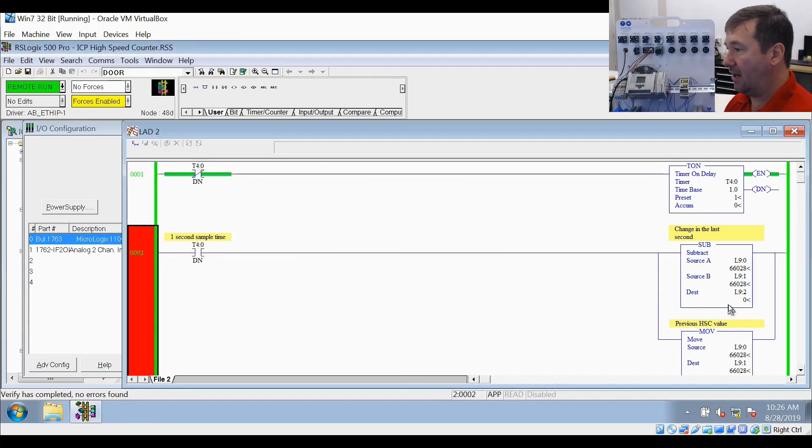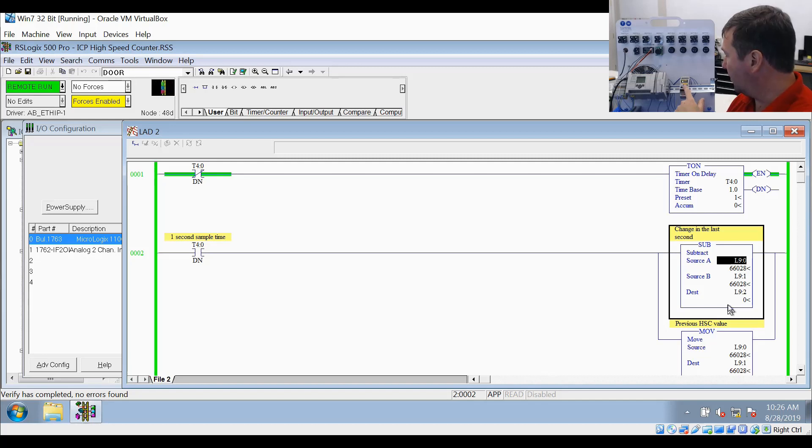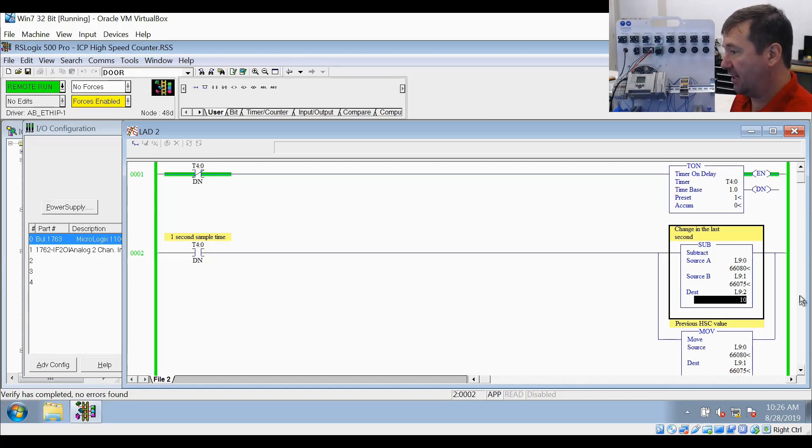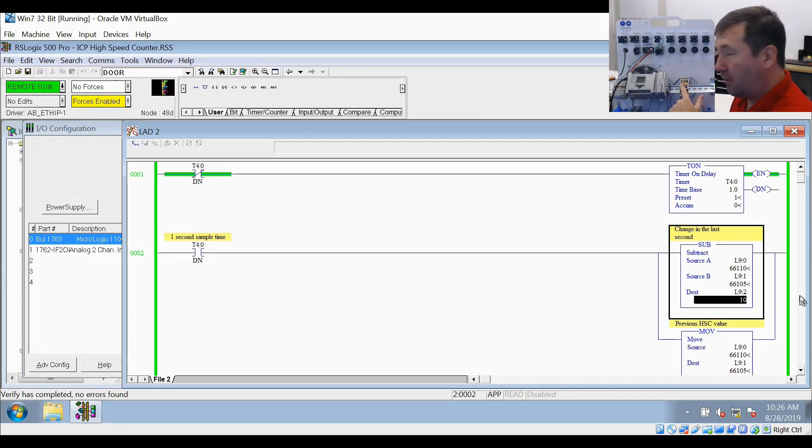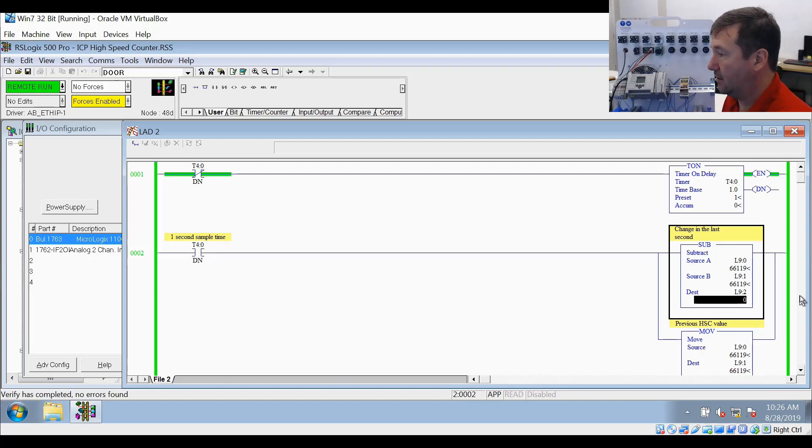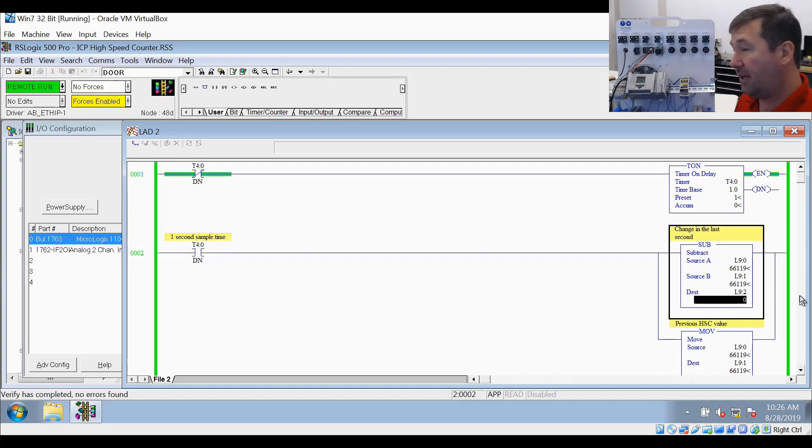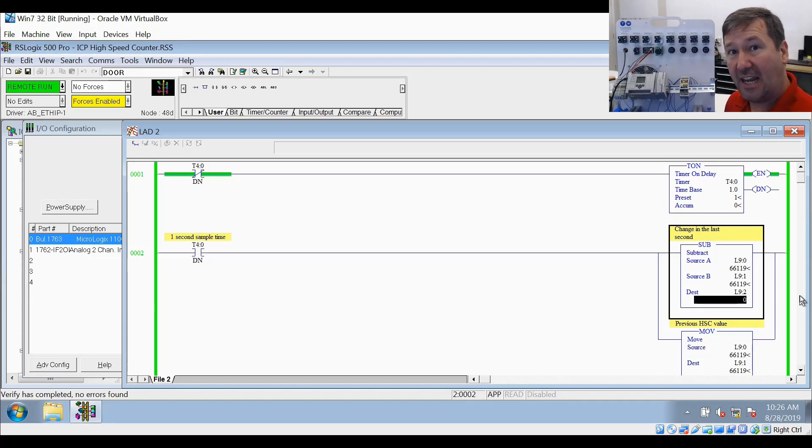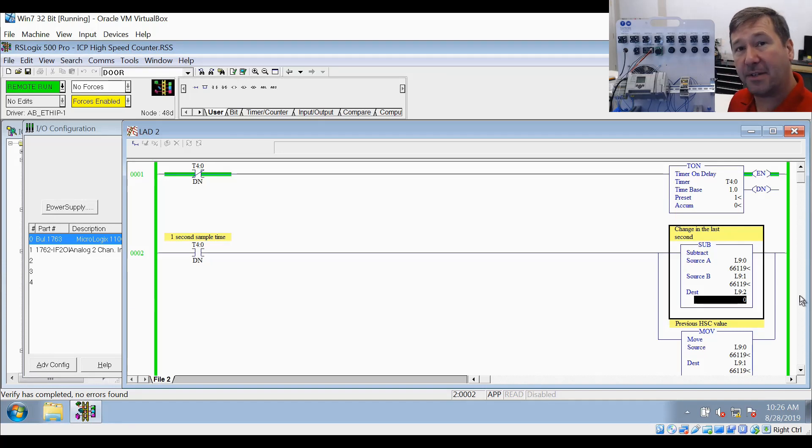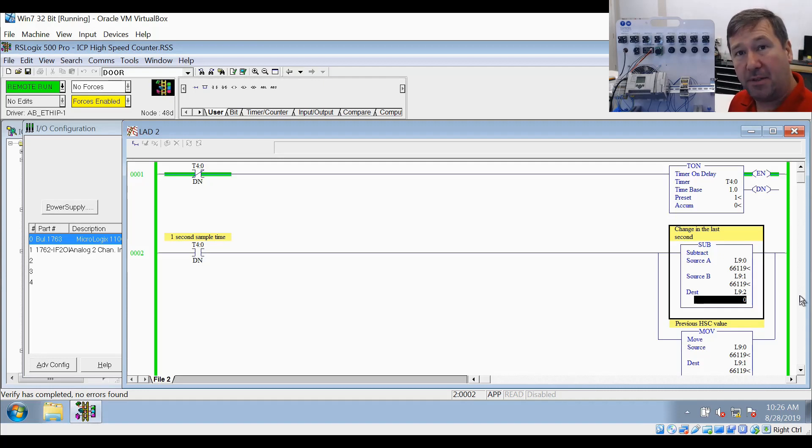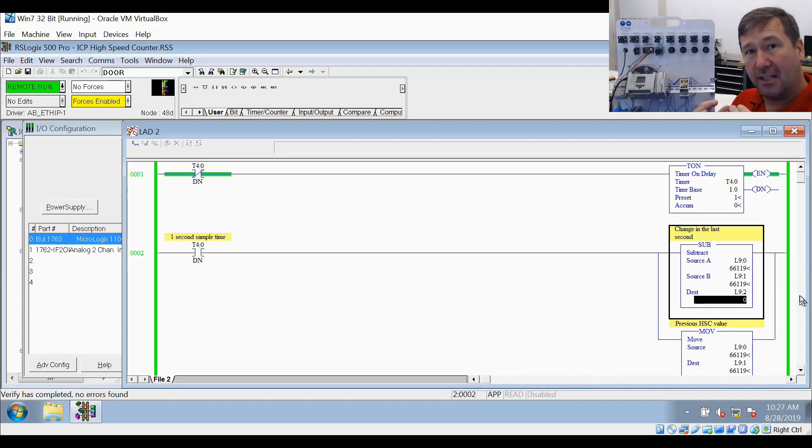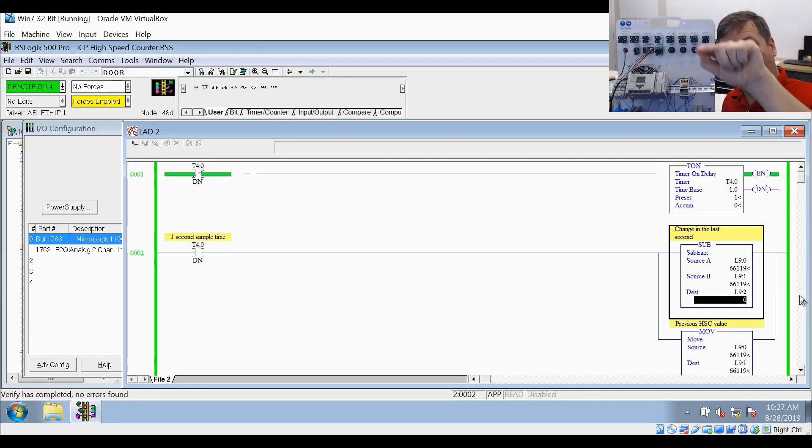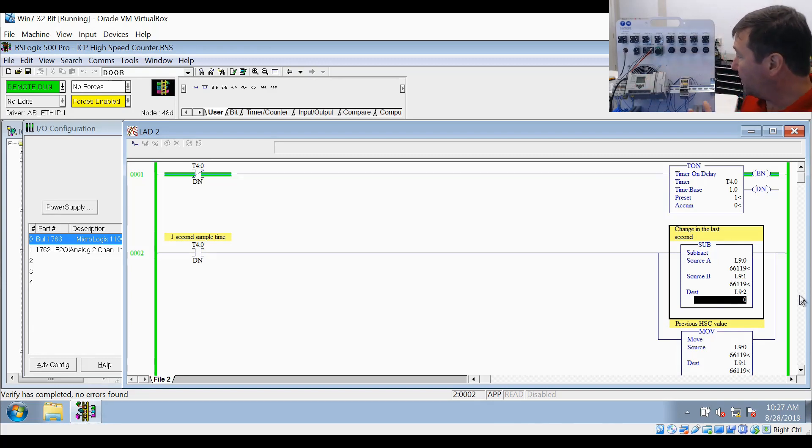Now our rate is zero because we are not going. We're going to put it in the forward direction. We're running 10 hertz, just like we should be. Now we're going to go up to 100 hertz. But you see, now our PLC did not go up to 100 hertz. It's actually showing mostly zero, occasionally bouncing around. That is because of that input filter setting. What that input filter setting is for is really to eliminate noise. It's hard to tell the difference between our high-speed counter pulses and a little ripple of noise, so it's filtering out our pulses.